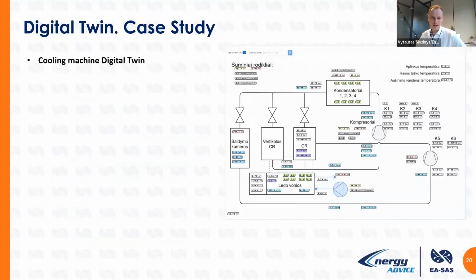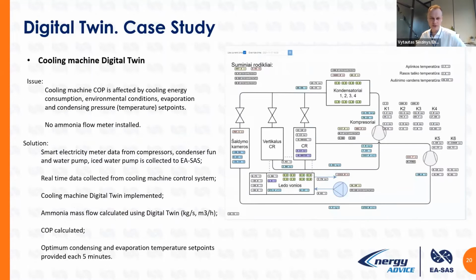So the key example of a digital twin for the cooling machine, which I will describe shortly here, is the compressor. We have 4 compressors, and all data is delivered from the SCADA compressor control system. Here we have one loop. It's a 2-stage machine. It's the condensing part. It is a receiver with ammonia inside, at about -2 degrees ammonia temperature. And this ammonia cools down water, and the water is recirculated through a pump.